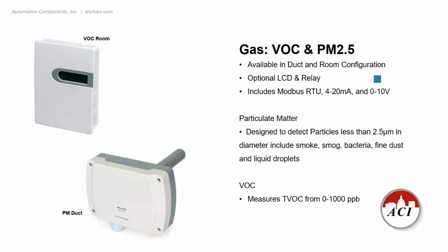Another slideshow showing specifically the VOC and the particulate matter sensor. We are seeing a lot of these that are going into spaces so customers or tenants know that the air is clean, and also a lot of that's the VOC room, and a lot of them PM duct sensors are used for a lot of the wildfires that are going on out west. So you'll mount this in the duct and it will prevent that smoky air being brought in because this sensor will sense that and not let the fresh air intake from the outside come in if it is at a certain level.